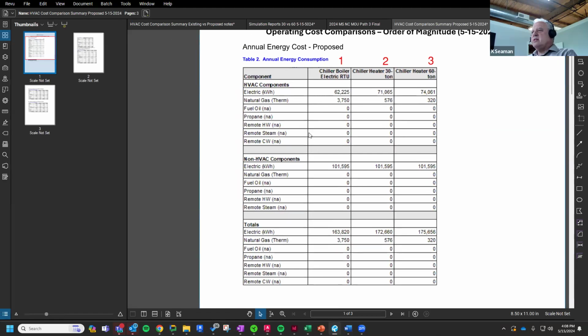And there is still boiler showing because neither option can fully take care of the gas heating load in the building on extreme temperature days. However, the 30-ton does a really good job at getting rid of the bulk of the gas heat. As you can see, it goes from 3,750 to a very small amount, actually about 600 therms, and I think a lot of that comes down to the fact that that's if you drive the thing to 0 degrees, like if you're just running it and trying to minimize your fuel consumption as much as you can. As we noted last time, it will carry the load till probably 25 degrees, and then it's going to need the boiler to help. But if you look at it on an annualized basis, there's not an immense amount of hours where we're below 25. Most of the hours occur above that. So it's capturing the fact that it's going to heat the building most of the time, except for those extreme days.